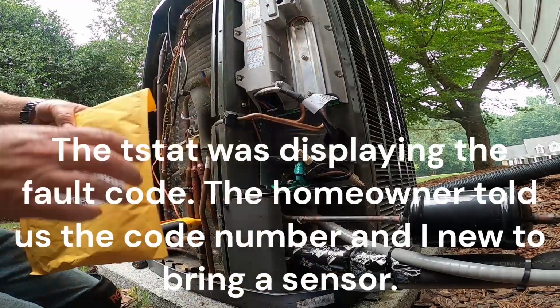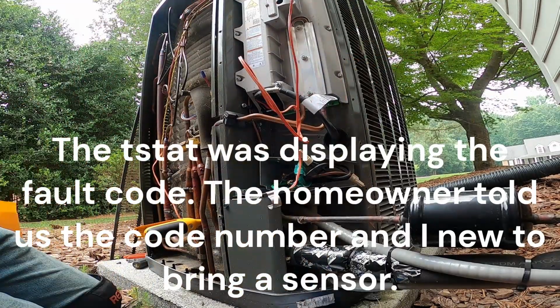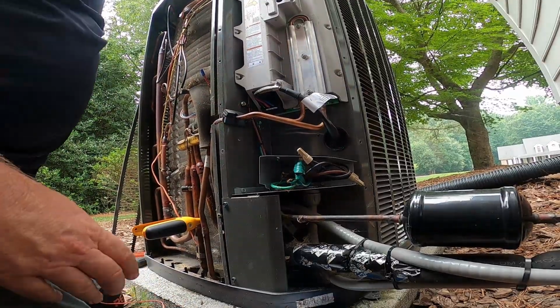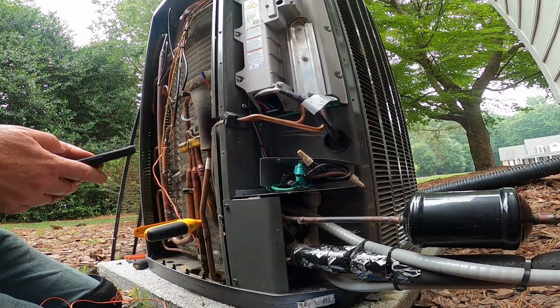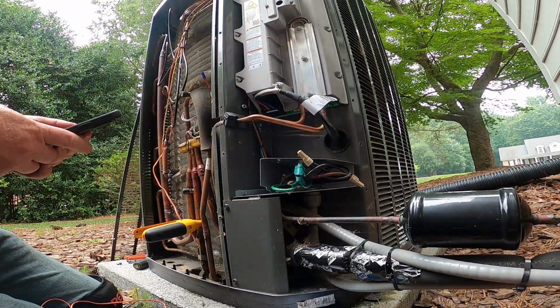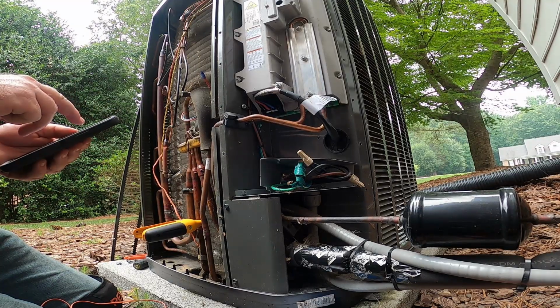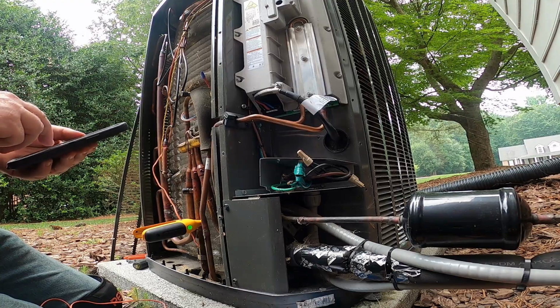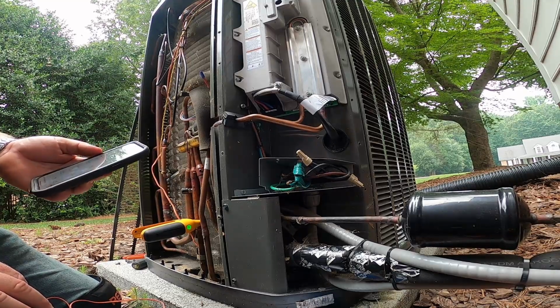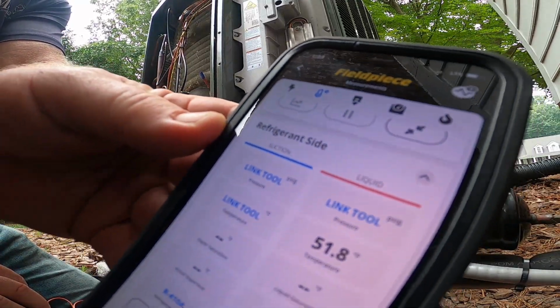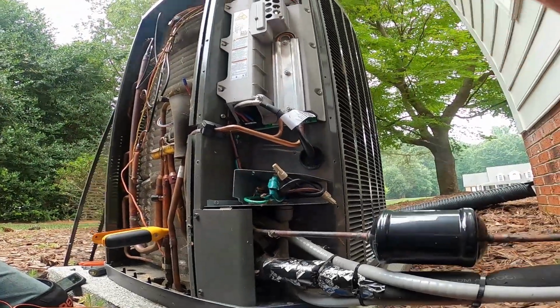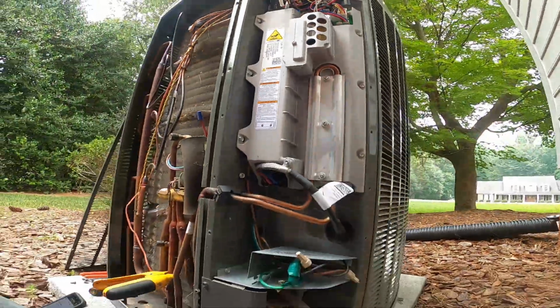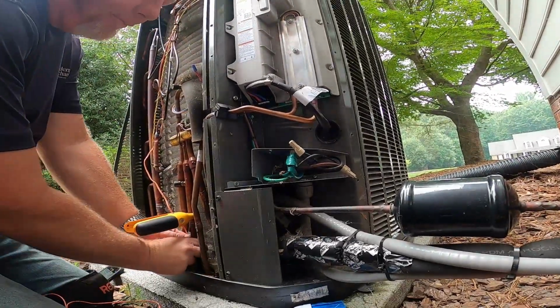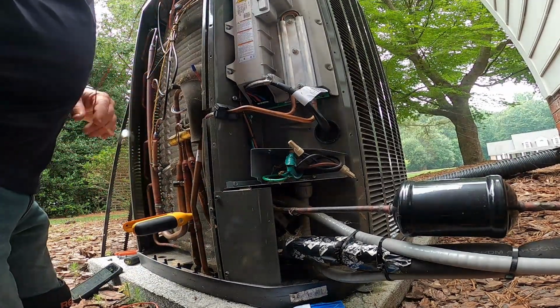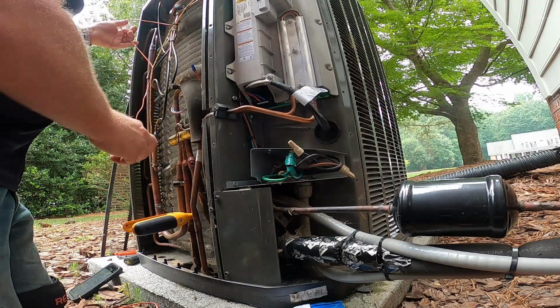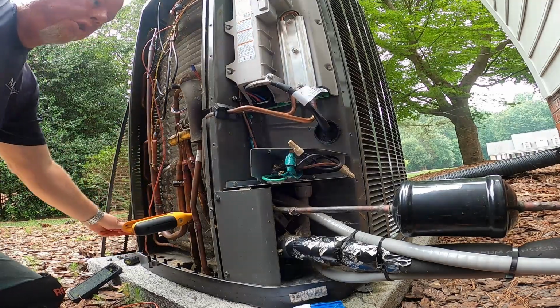I brought a sensor with me because I knew I was going to need it, and right there it is. But real quick, I'm going to pull up the app and see what my temperature probe is telling me that line temperature is. 52 degrees. So right there, 52 degrees, and our display is telling us that the suction line temperature is 118 degrees. So we have a bad sensor. We'll swap it out real quick. This system was installed last year, so this will be under warranty. No charge.